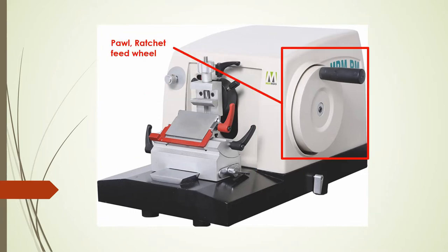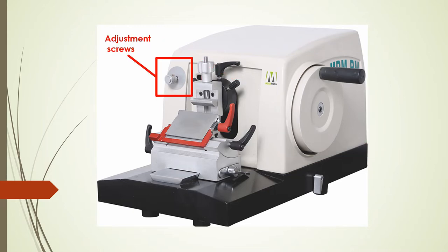Next, we have the pawl and ratchet feed wheel, which are used to adjust the tissue block holder back and forth — they can be adjusted counterclockwise or clockwise. And lastly, we have the adjustment screws, which adjust the thickness or how thin you want your sections to be — anywhere between 3, 5, 10, 15, or 20 microns.